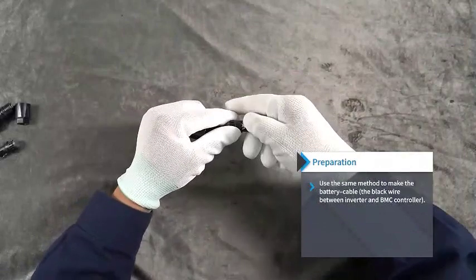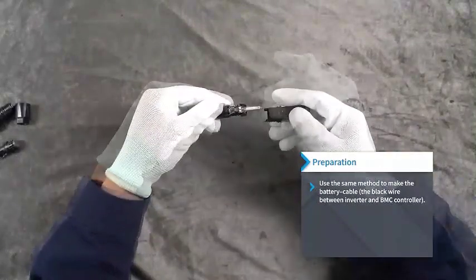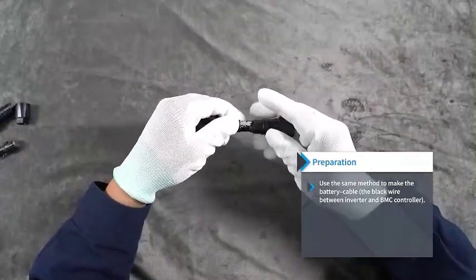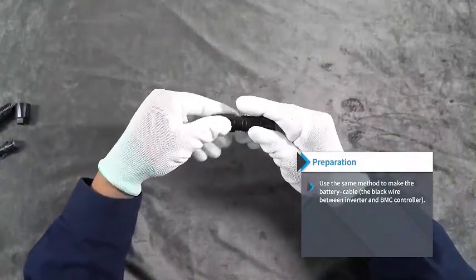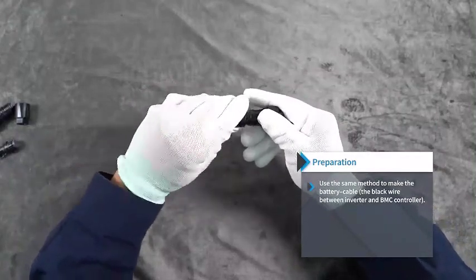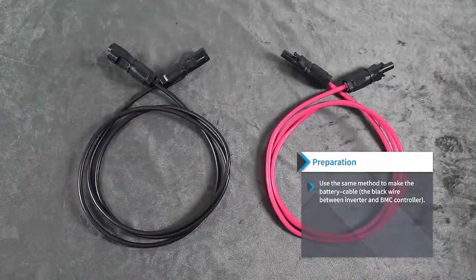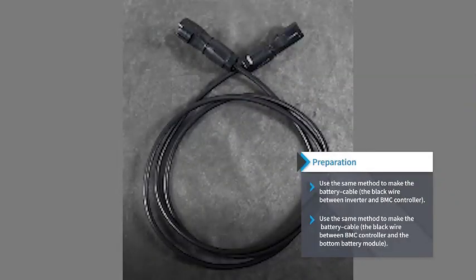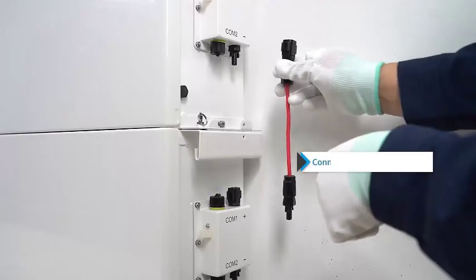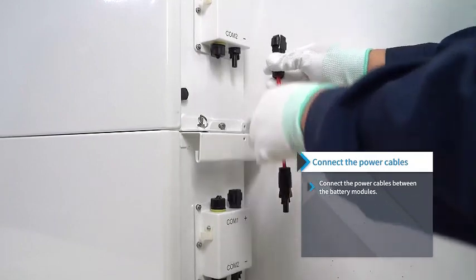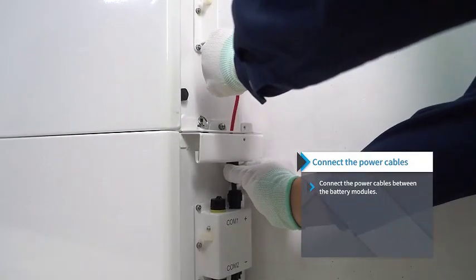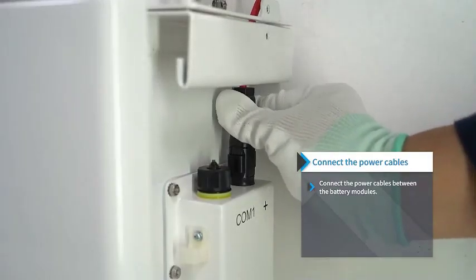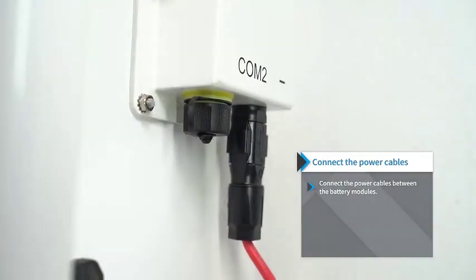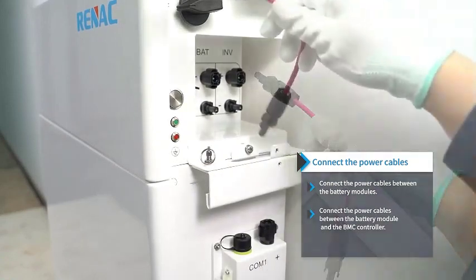Use the same method to make the battery cable, the black wire between the inverter and the BMC controller. Use the same method to make the battery cable, the black wire between the BMC controller and the bottom battery module. Connect the power cables between the battery modules. Connect the power cables between the battery module and the BMC controller.